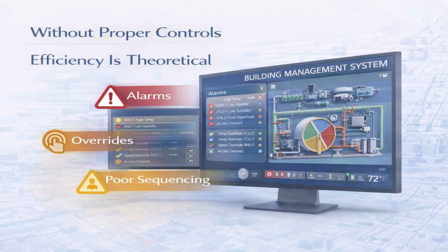Controls are not optional accessories that are added after the HVAC units have been selected. They are a core part of how the system performs. Even the best selected units can behave poorly if the control logic is weak or mismatched to the system design. Poor control strategies often lead to problems such as simultaneous heating and cooling, unstable or drifting space temperatures, excessive energy consumption, and frequent alarms or manual overrides through BMS.